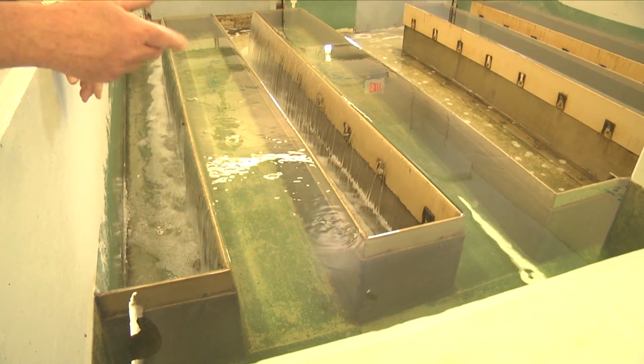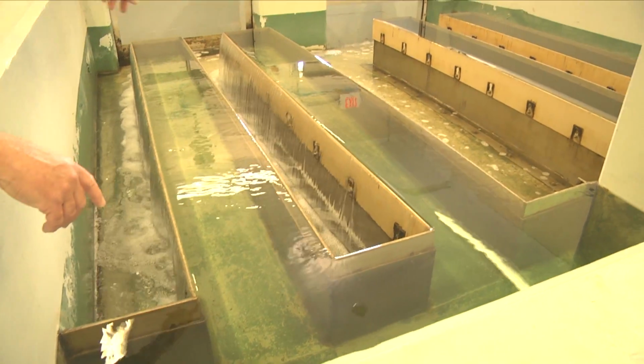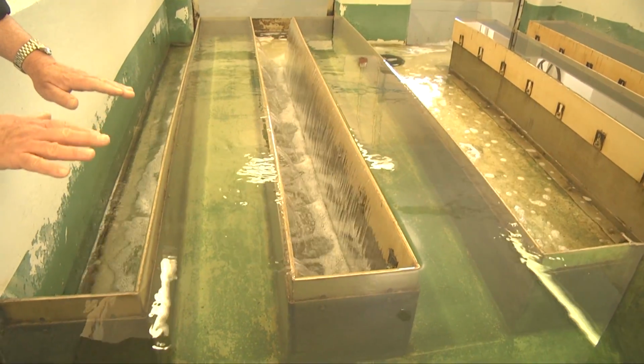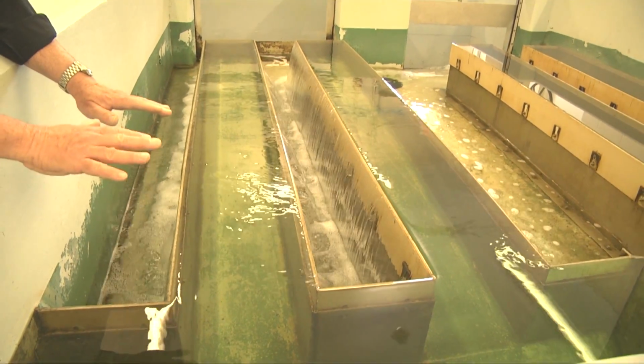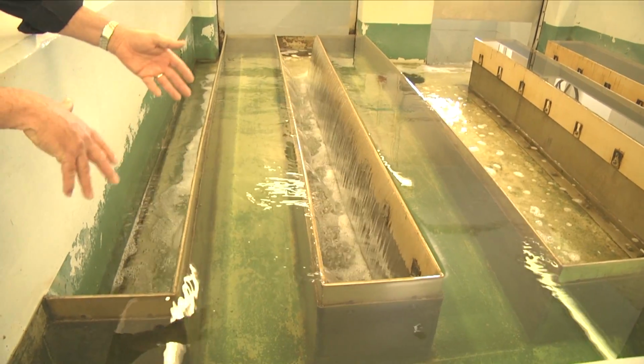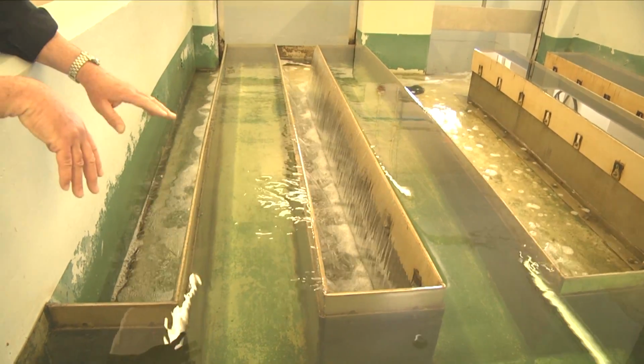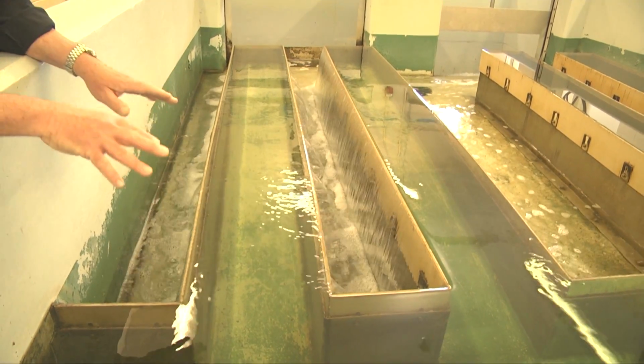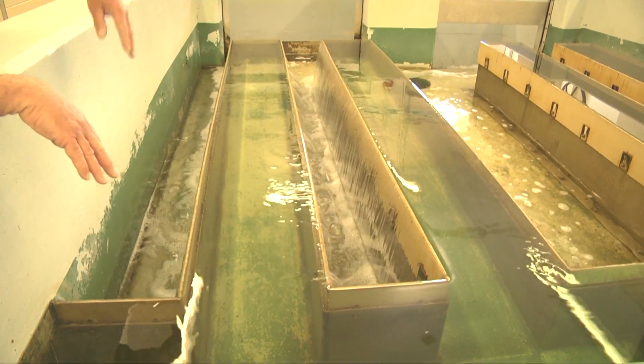This is the after bay past the chlorine system. It goes into these two finger channels, and the finger channels, what they do is they keep the depth of the water constant, and then they cascade over slightly, so any kind of solids or anything that may have gotten past the filters will settle out in here, and this is periodically cleaned.